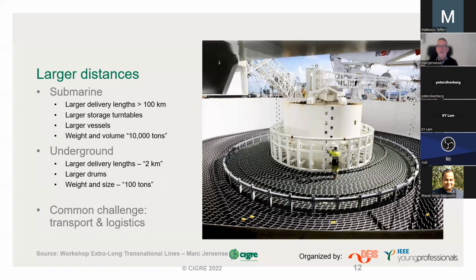For underground cables, typically the transmission system operators say we do not want so many field joints, because joints are still seen as the weaker point of a transmission system. So the fewer joints, dear manufacturer, the better. That technology there has nothing to do with high voltage, it's just transport and logistics. What is the maximum length I can transport on a drum on the roads in a certain country?